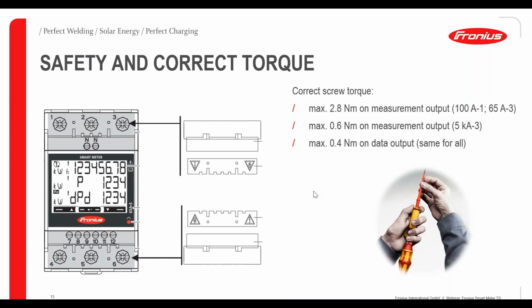Moving forward, when it comes to installation of smart meter in a PV system, of course, safety is always the most important thing. So we got two different protection covers here on these new smart meters. The first cover is the protection cover, which goes over the connection terminals of the phases. So we have pin 1, 2, 3, and 4, 5, 6. We cover these connection terminals to secure them when you as an installer are working on these data communication pins to connect the smart meter to the data communication card of the inverter. Then we have sealable terminal covers, which go over all the connection terminals and secure everything here.